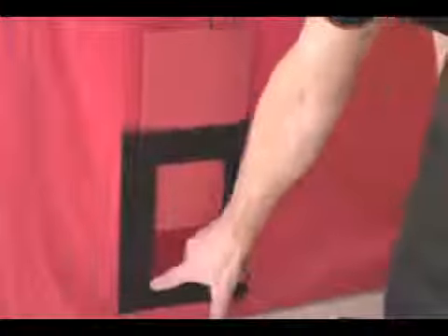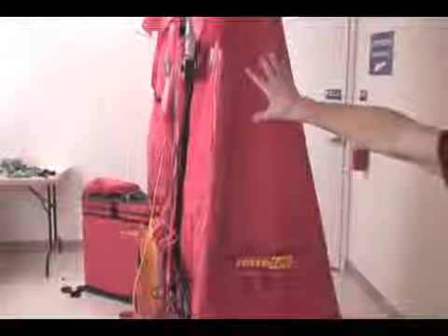On our simulator here, we've got three sliders, and they slide up and down a 4 by 8 inch hole. We've got this one open up halfway, so we've got roughly 16 square inches here, 16 square inches on the other side, a little bit of leakage here and there around the panel and so forth, so we're expecting to measure at least 32 square inches.